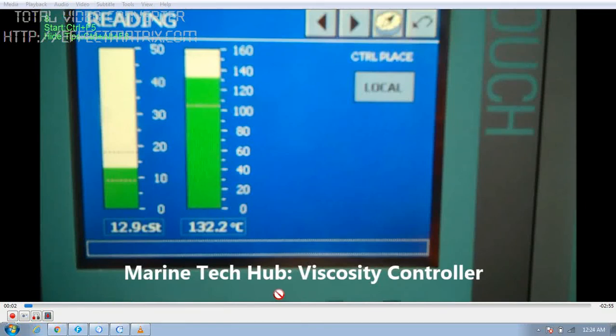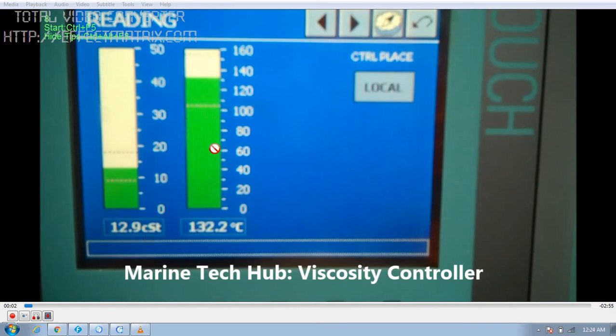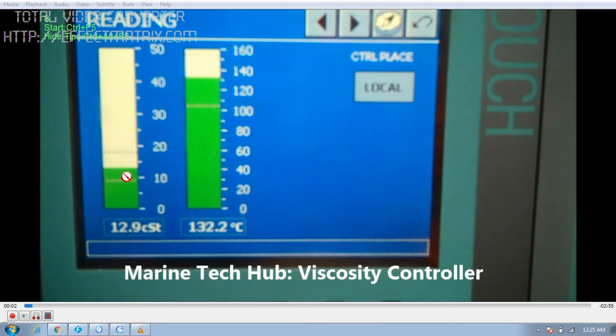Welcome to Marine Tech Hub. Today I will be explaining you about the viscosity controller. In this picture you can see this bar shows the viscosity. Right now it is 12.9 centistokes and the temperature of the fuel oil is around 132 degrees. So to get a viscosity of 12.9 we need to heat the HFO, that is heavy fuel oil, to 132 degrees. Since we want a viscosity in the range of 13, that is the set point which we have given here.